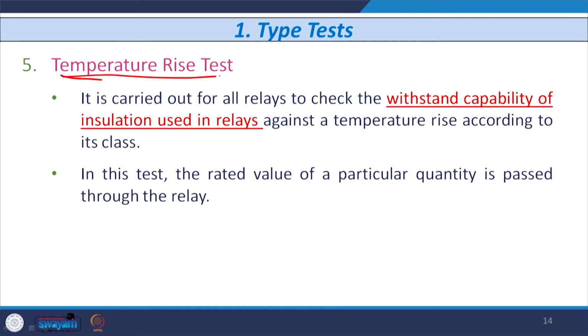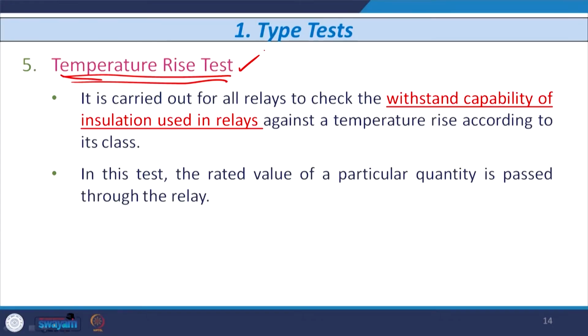The next test is known as the temperature rise test. This type of test is carried out for all the relays just to check the withstand capability of the insulation used by the relay. Basically, we know that whatever contacts and coils are there in a relay have to be manufactured or designed based on a certain insulation class. So, there is a need to check the withstand capability of the insulation used in the relay, particularly with reference to the temperature rise. When you give the normal current or a certain value of current, what is the temperature rise with reference to the current flowing in the contacts or coil of the relay? That needs to be tested, and that comes under the temperature rise test.